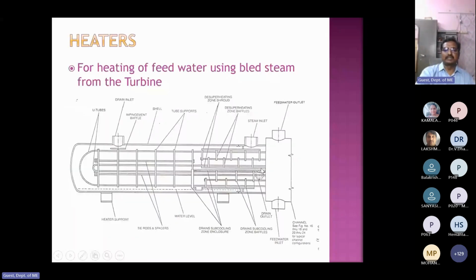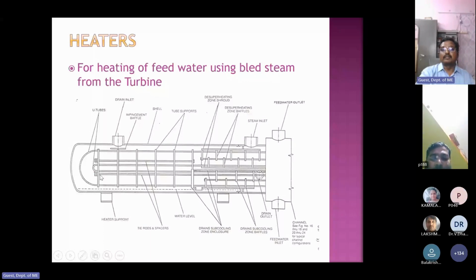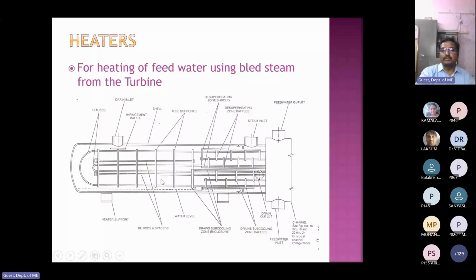This is a cross-section of the LP heaters and HP heaters. Both heaters have similar construction. Water flows through the tubes. There are small tubes. Water flows through the tube like this, changes direction and goes down like this. This is the inlet. Water comes like this and flows like this, and again goes to the outlet. This is the outlet. So this is the water circuit.